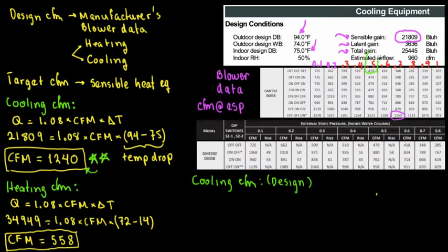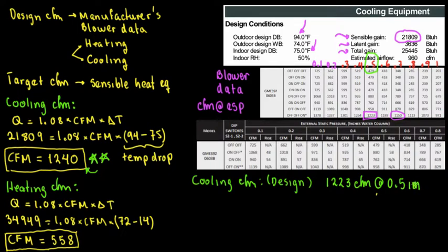At 0.5 inches of static pressure, it complies with our target CFM. So the design CFM is 1,223 CFM at 0.5 inches of water column (or water gauge). Now, when we talk about an air handler or furnace, we need to consider all components contributing to resistance.